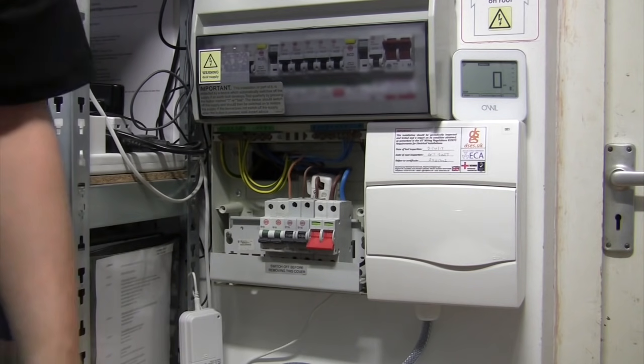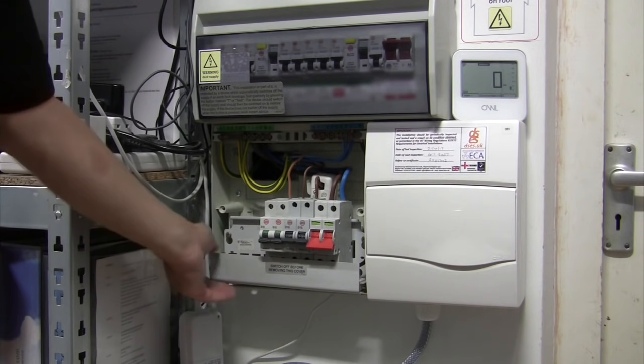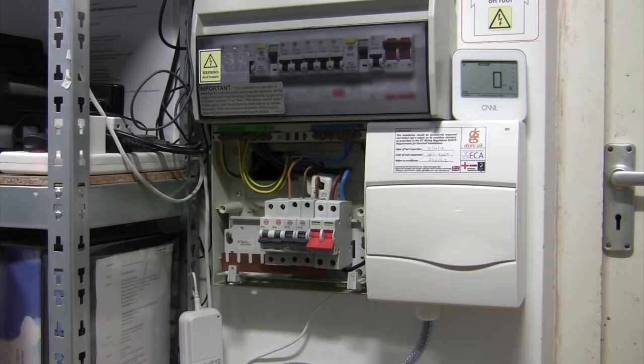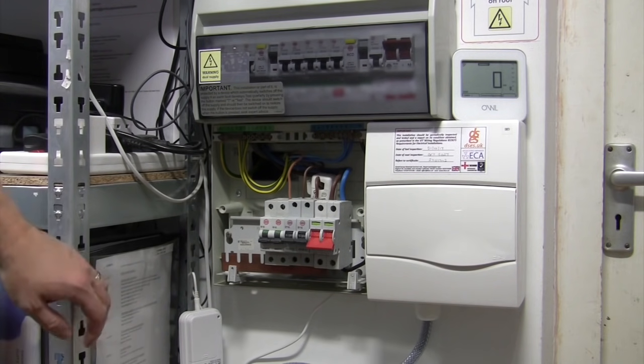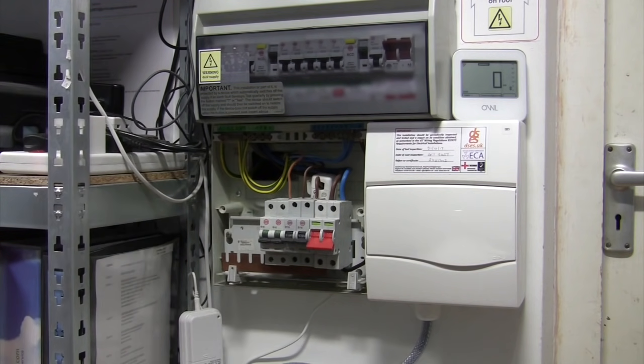I'm going to have to cut down the busbar to fit this in, but there's a spare 16 amp breaker here which can drive the thing, and once fitted it'll protect DB1, 2 and 3, so type tested or not, I'm going to sleep easier knowing my installation is surge protected.